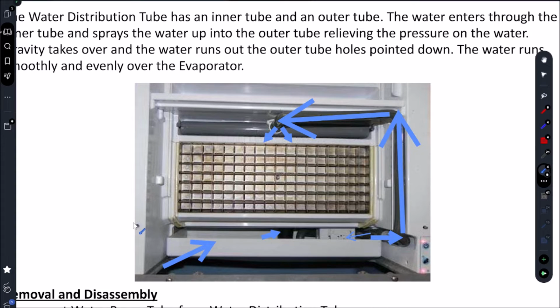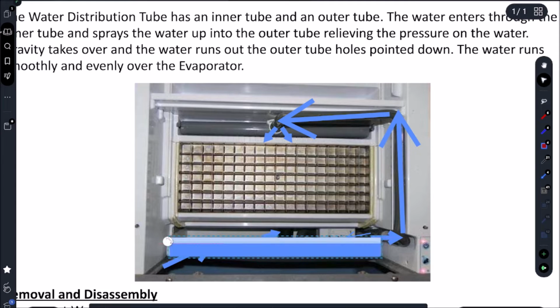So we always rule out the water circuit, then the electrical circuit. Once we've verified that our pump's good and our coil is getting cold, water is going to distribute through there. So let's say we have this much water. As water starts to distribute from the trough, from the pump to the manifold down onto the coil, this water level here is going to drop as the water starts to turn into ice on the coil.